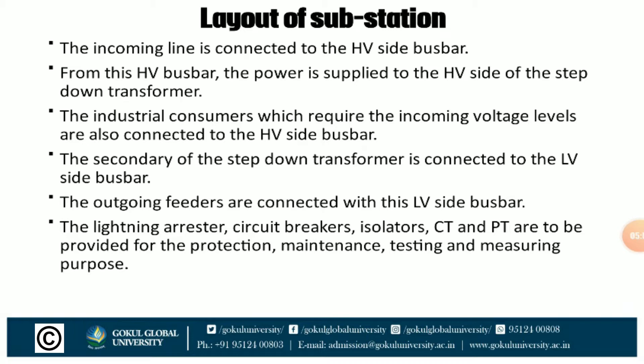Now we discuss about the layout of substation. The incoming line is connected to the HV side bus bar. From this HV bus bar the power is supplied to the HV side of the step-down transformer. Industries or consumers which require high voltage levels are also connected to the HV side bus bar. The secondary of the step-down transformer is connected to the LV side bus bar, and the outgoing feeders are connected with this LV side bus bar. Lightning arrestors, circuit breakers, isolators, current transformers, and potential transformers are provided for protection, maintenance, testing, and measuring purposes.